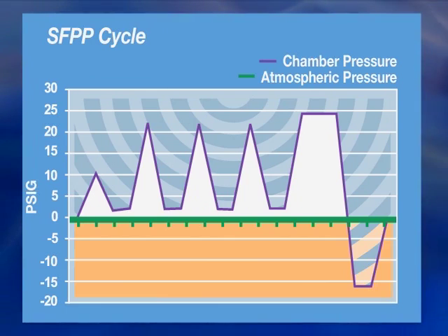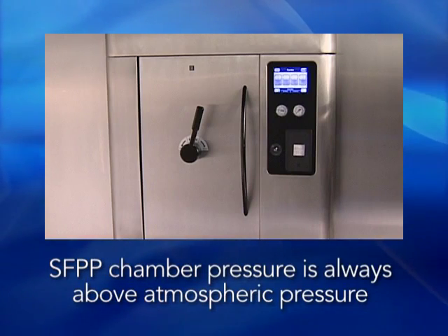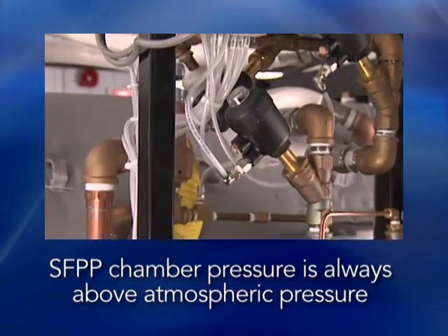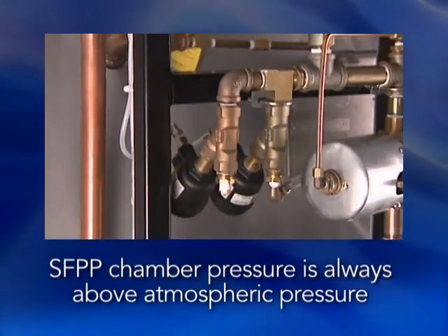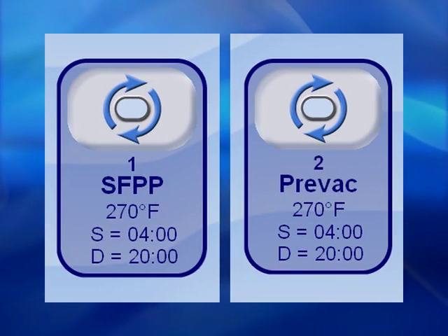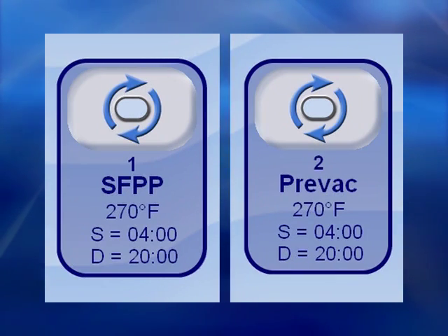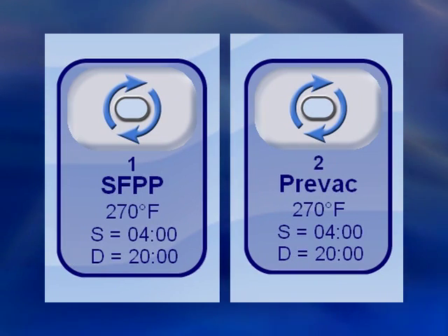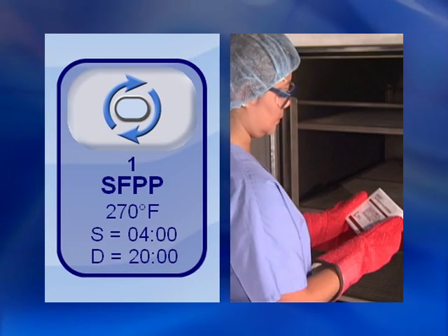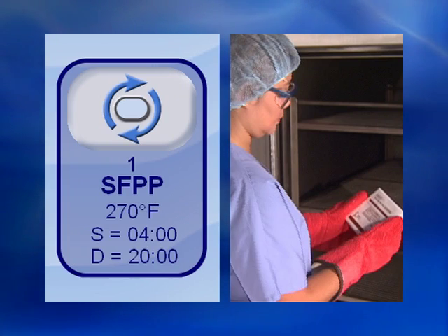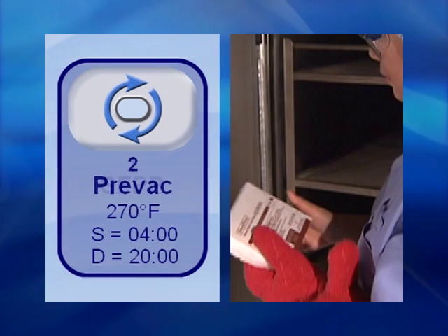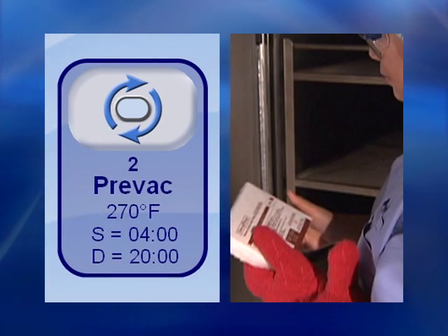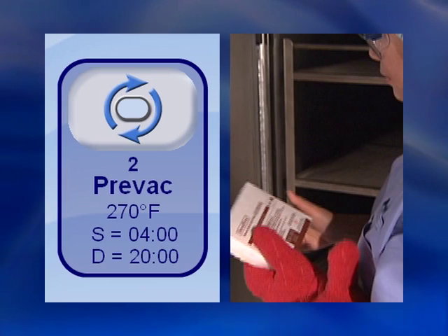During the SFPP cycle, the conditioning phase is always at pressures above atmospheric, and air cannot be drawn back into the chamber during the conditioning phase of the cycle, even if there are leaks in the plumbing or gasket. For processing purposes, the SFPP and Prevac cycles are considered equivalent dynamic air removal cycles. If your sterilizer has the SFPP cycle and you use it instead of the Prevac cycle, you will not need to run a Bowie Dick or DART test.